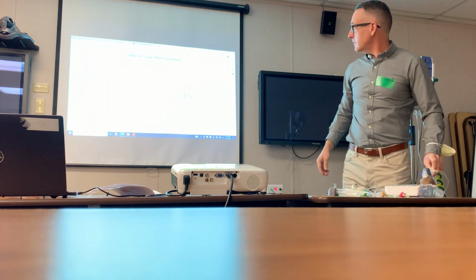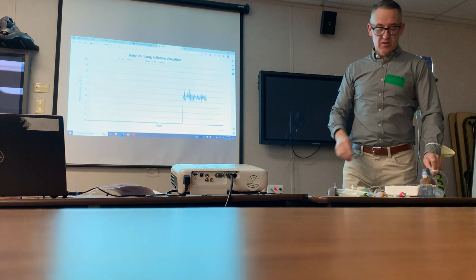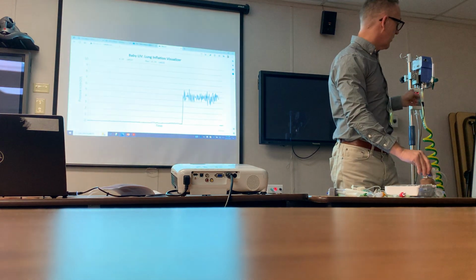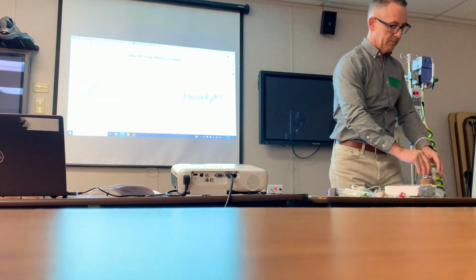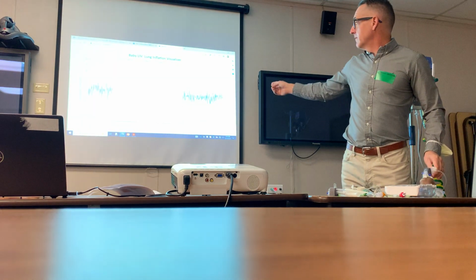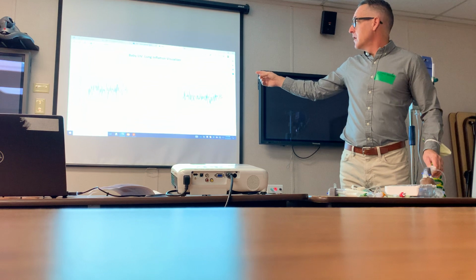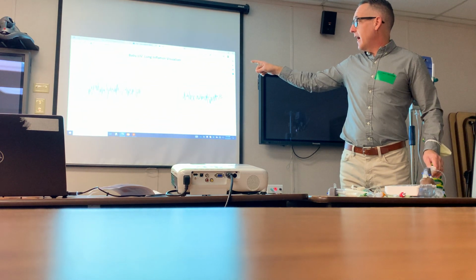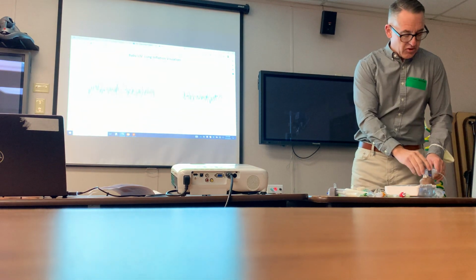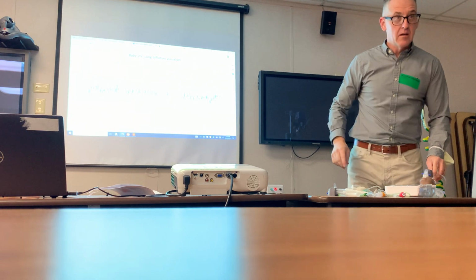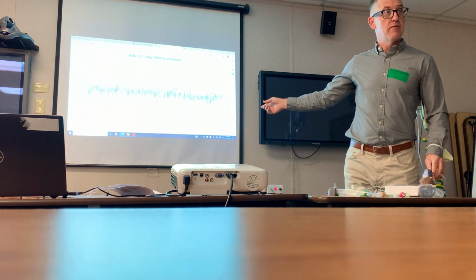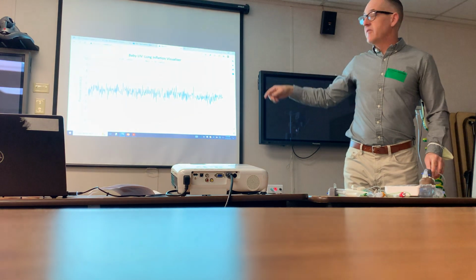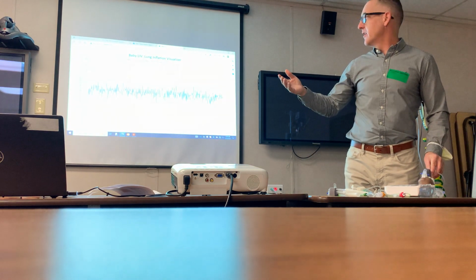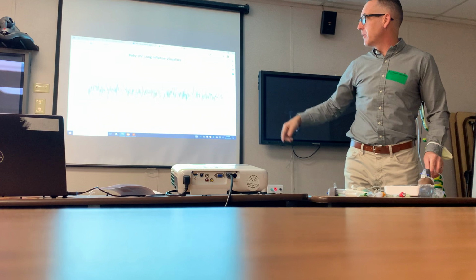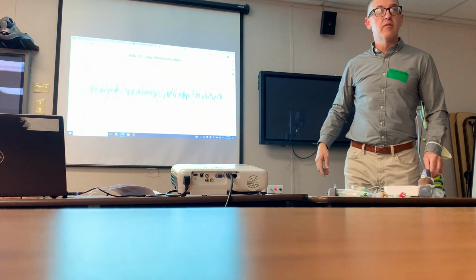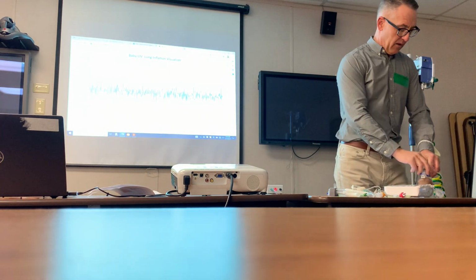Okay. So I have this at 5 centimeters of water pressure. When I look at my manometer, it says what? 5. When I look at the screen, it says what? 5. Now, when we look at the screen, we also have these vibrations. That's the oscillatory effect for the bubble CPAP. That's what we're going for, obviously, for the bubble CPAP. That's that vibration, plus or minus 1 or 2 centimeters of water pressure. So you can see sometimes it jumps above 6, sometimes it drops below 4, but the mean is about 5.